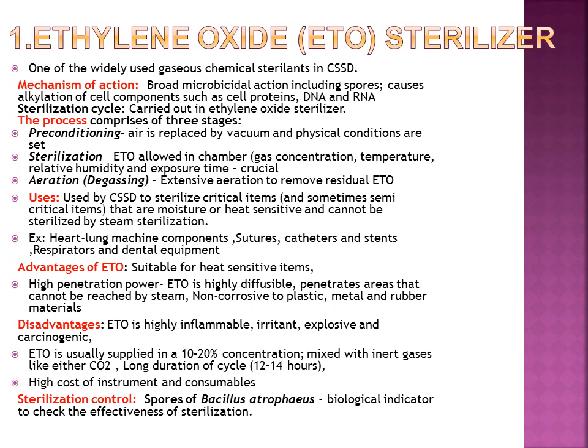So ETO is usually supplied in 10 to 20% concentration mixed with inert gases like CO2. The long duration of cycle, 12 to 14 hours. High cost of instrument and consumables. Sterilization control: spores of Bacillus atrophaeus is the biological indicator.